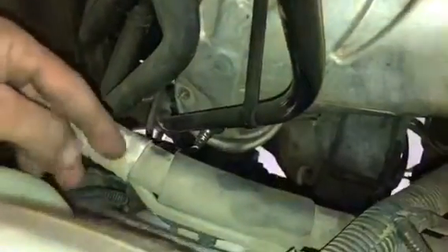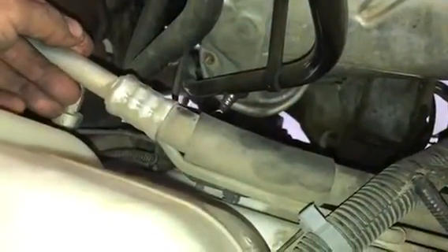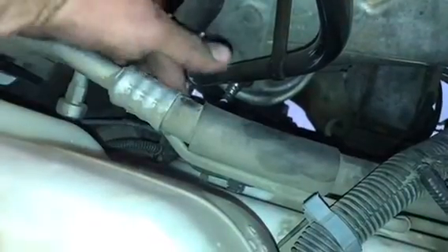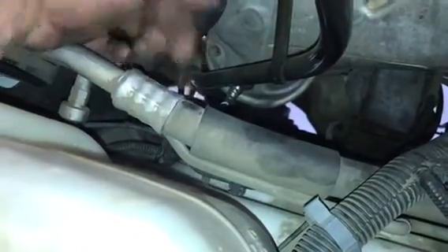It'll be a lot easier to look. Another area that's really common for leaks are these metal hoses. Right where the crimp is, it turns to rubber, and after time they might vibrate loose or come loose. So look for wet areas around there, maybe anywhere where it's rubbed up against something.